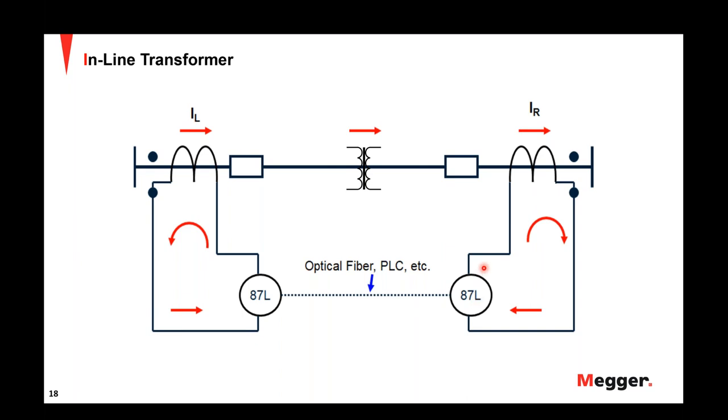So when you perform testing of such a system, you would have to keep in mind and make sure all the compensation is provided with respect to transformer connection, CT connection, and all the other significant attributes, and then you do your injection, right? Not only that, you would also have to perform additional tests with respect to harmonic restraint and harmonic blocking, since a transformer is involved, with respect to the energization of the transformer and transformer inrush.